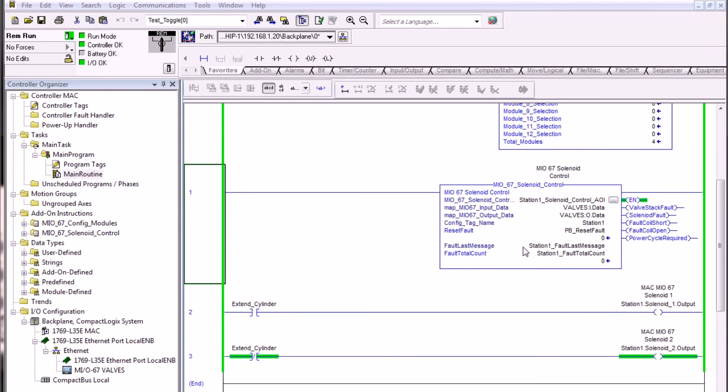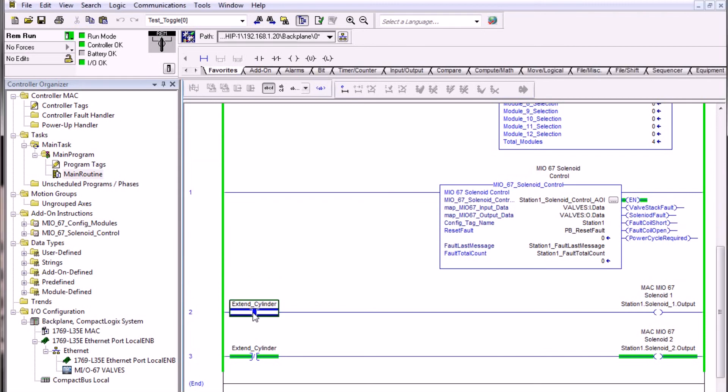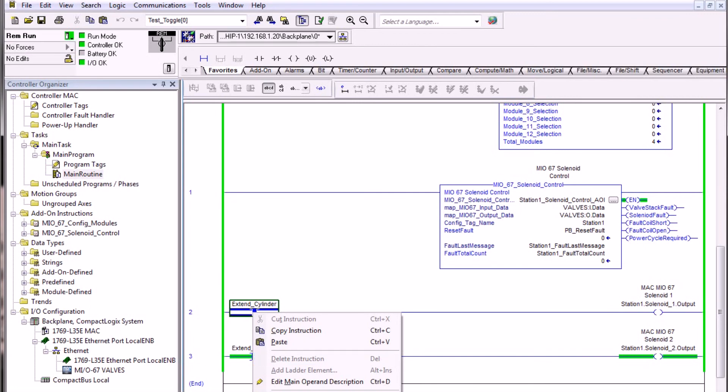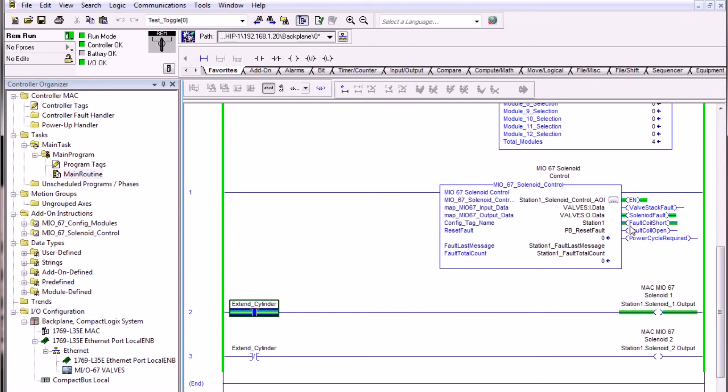Next let's take a look at one of the examples of how the fault coil short works. We've artificially created a coil short on solenoid one. Since we have ladder logic here to extend the air cylinder, let's go ahead and toggle this bit. When we toggle this bit, since we've created a fault coil short condition, we have basically now illuminated the output solenoid fault and the type of fault that's been detected. A fault coil short has been indicated.